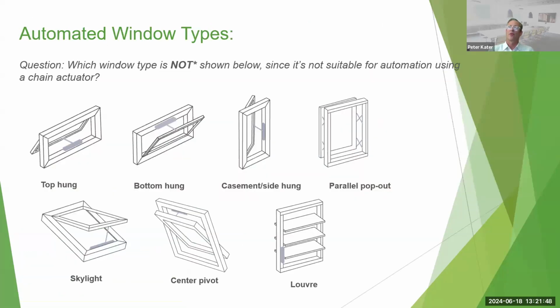The types of operable windows which can be automated with chain actuators, the ones that you normally see on public buildings: top hung awning type, bottom hung hopper type, typically inward projecting, side hung casement windows. You can automate parallel pop out vents, curtain wall facade, for example. Skylights, that's an important one, particularly for smoke and heat evacuation. You can have center pivot windows and louver systems. So we have a different actuator that operates the louver system. Typically, that's a special type.